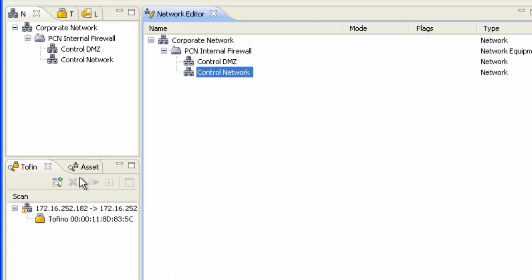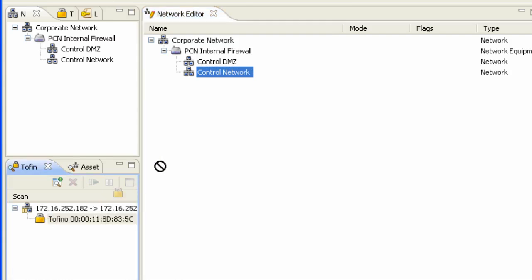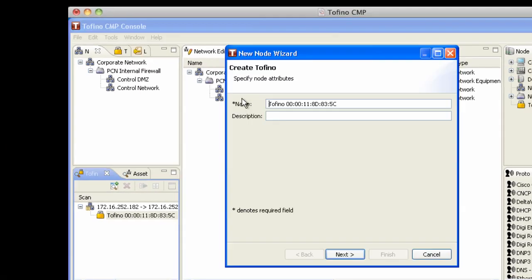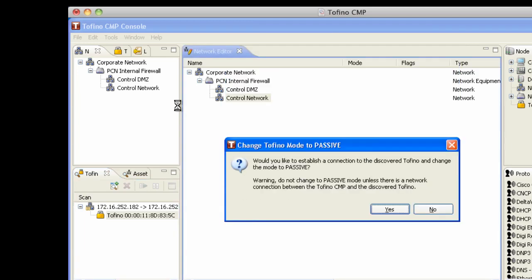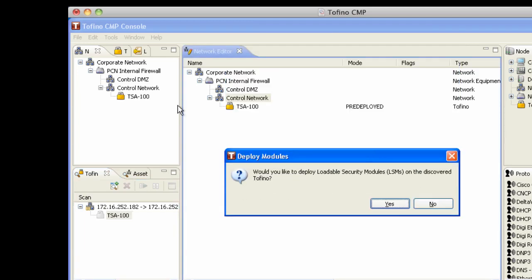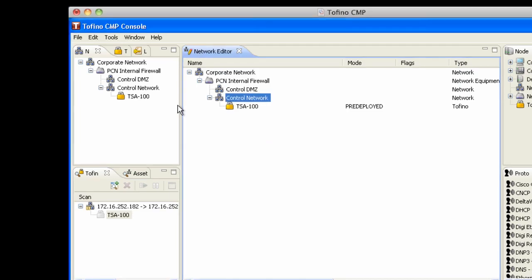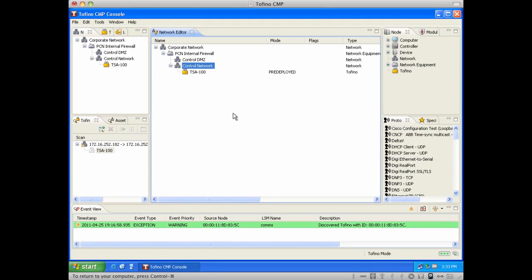At this point, the CMP has discovered our new Tofino, which is connected in line between our Factory Link server and client. I'm now going to drag it up into the control network, provide some basic information, and turn on the communication between the CMP and the Tofino security appliance. This will allow us to do further configuration and build rules.